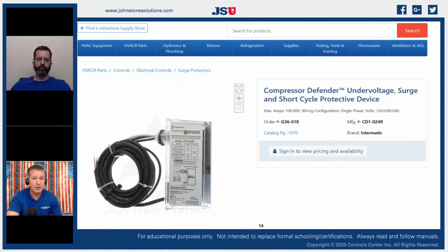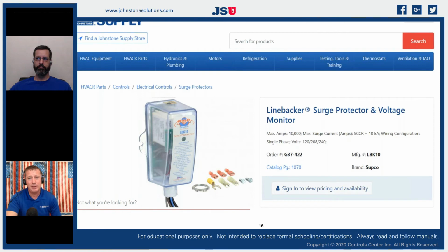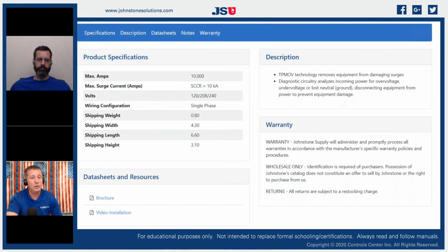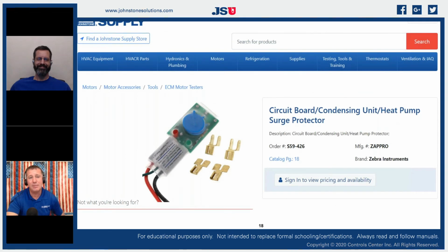There's also the Intermatic Compressor Defender. I think Bob Vila sponsors that one. So that's a real popular one that's out there. It's rated for 120, 208, 240. It's rated 100,000 also. So nice little add-on component. We've got the Linebacker, which the downfall with that one that I've seen is it's a 10,000 rating, but it's still a good little piece. That's the Supco LBK10. So that one's been around for a little while and become a pretty popular surge protector. It's a 120, 208, 240 as well. We have the Zebra, and the nice thing about Zebra is they have units that are for, I would consider, smaller capacities.